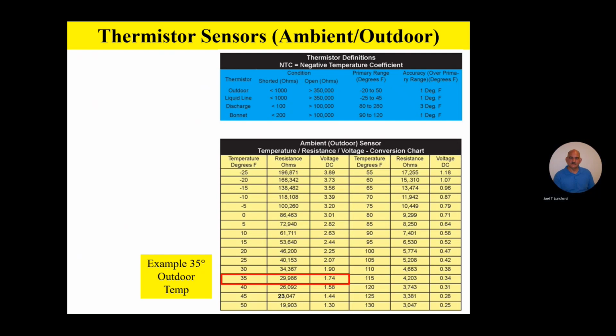So just remember, at any given known temperature, you can unplug the sensor from the board, and you can read the ohms by taking your ohm meter. And in this example, at 35 degrees outside, the ohms should be about 29,900 ohms with it unplugged off the board. Now hang on a second. If I take that sensor and plug it back onto the board at 35 degrees, and I set my voltmeter to DC volts, and I take my needlepoint meter leads and dig into the back of that harness, I should read 1.74 volt DC with the sensor plugged back onto the board.